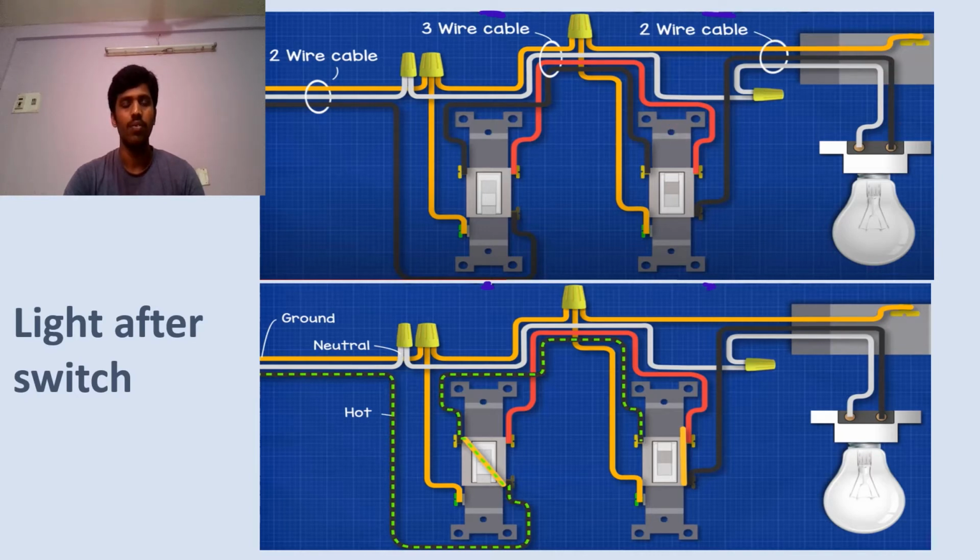The neutral wire which is coming from the outside wire is given to the wire connector of switch 1, and it passes through the wire connector of switch 2 casing, and it finally reaches the other terminal of the metal light fitting, and it passes through the ceiling. And there is one more wire called the ground wire which is given to the wire connector which is present in the switch 1 casing, and given to the wire connector which is present in between two switches. Finally, it reaches the screw which is given to the ceiling to provide proper grounding.